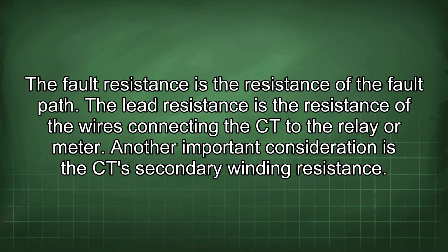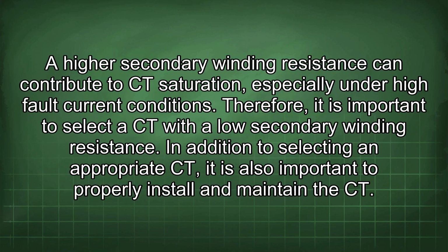Another important consideration is the CT secondary winding resistance. A higher secondary winding resistance can contribute to CT saturation, especially under high fault current conditions. Therefore, it is important to select a CT with a low secondary winding resistance. In addition to selecting an appropriate CT, it is also important to properly install and maintain the CT.